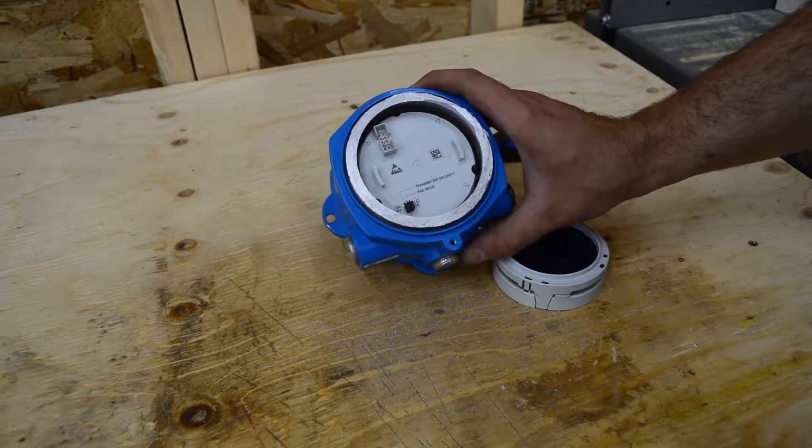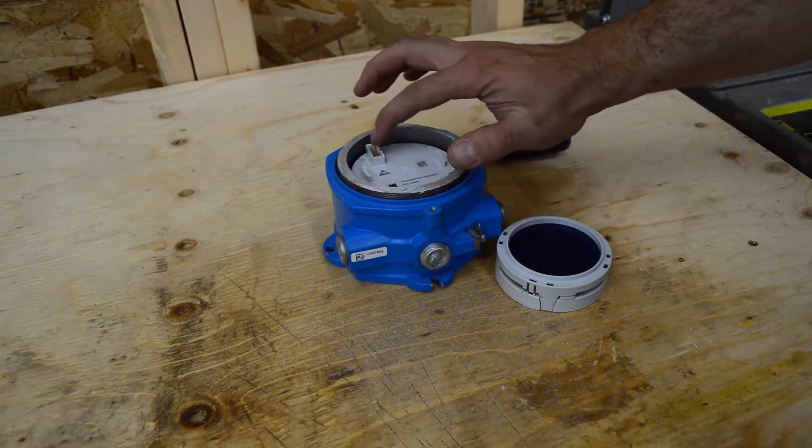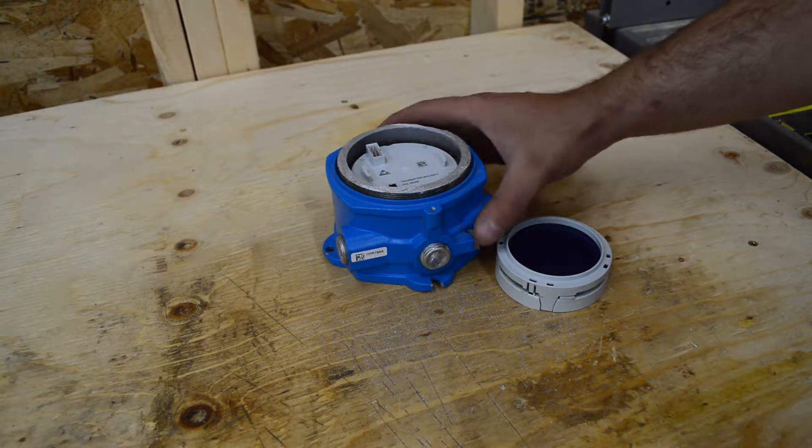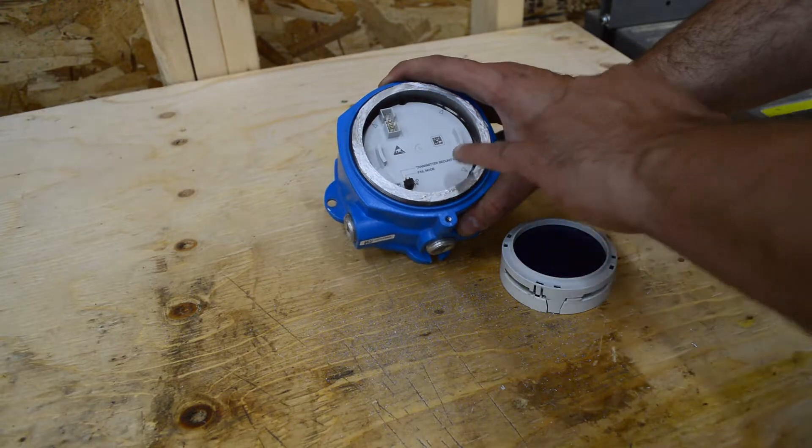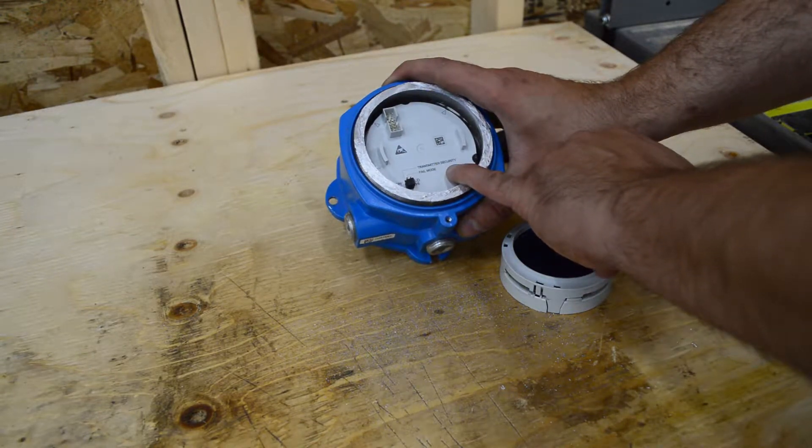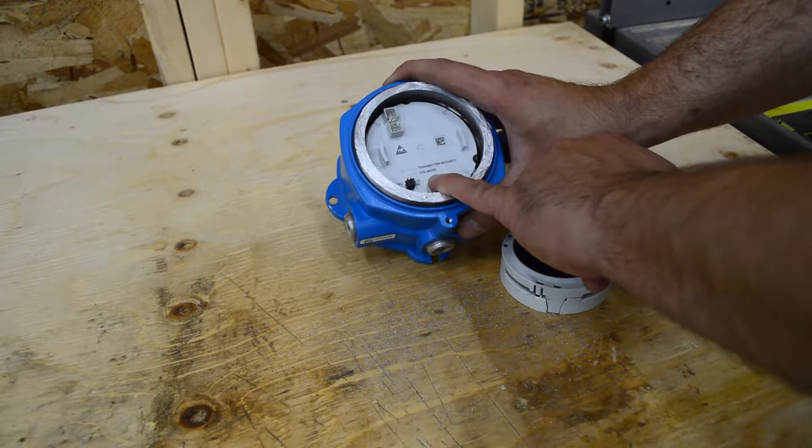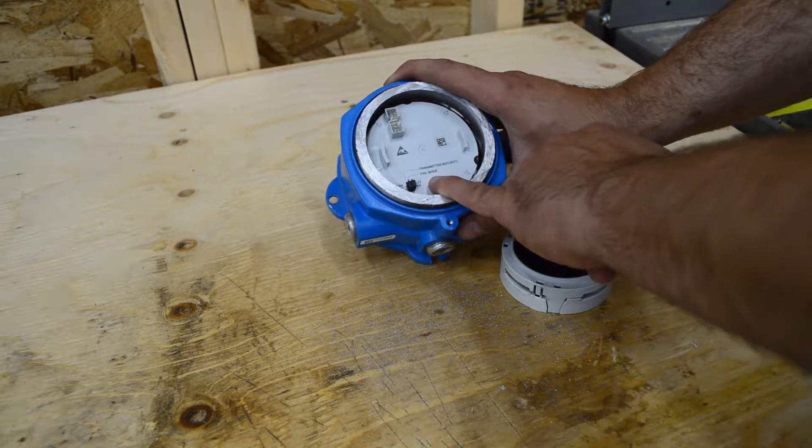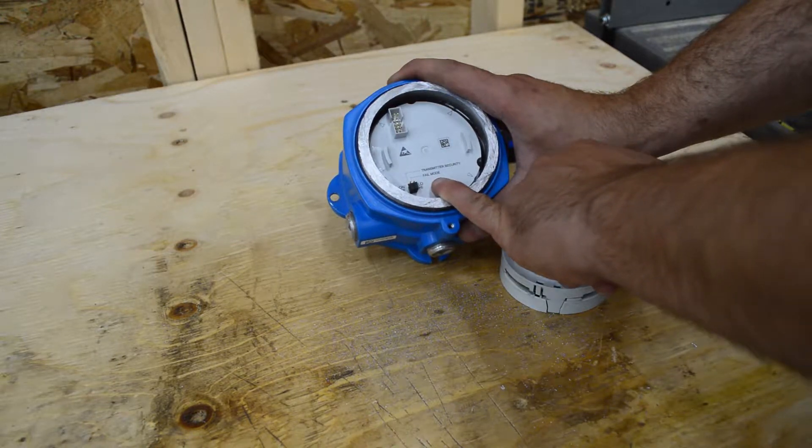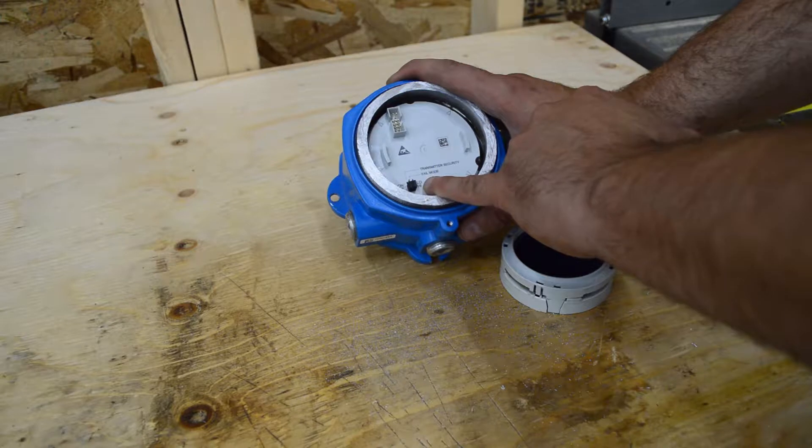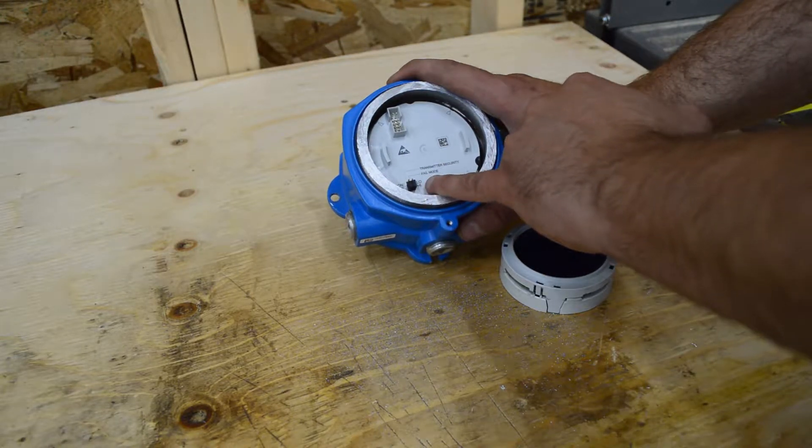So, pretty simple transmitter there. You got your screen pins there, security, and failure mode. So if you lose the RTD or the thermocouple, if there's a break in the line or something, it'll tell the transmitter to send out a high or low signal based on this jumper here.